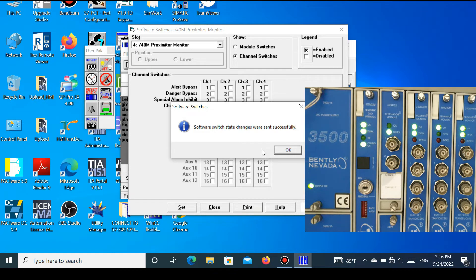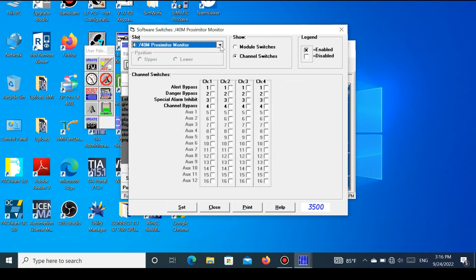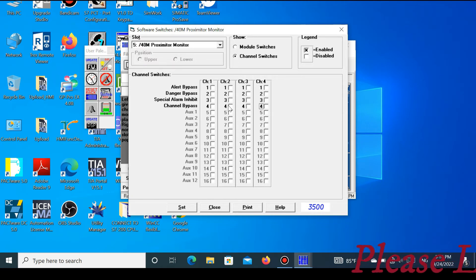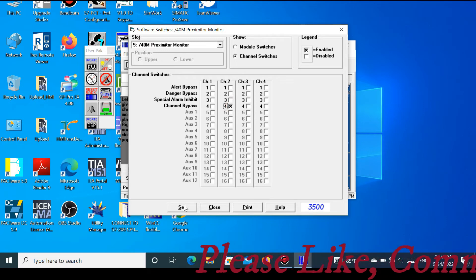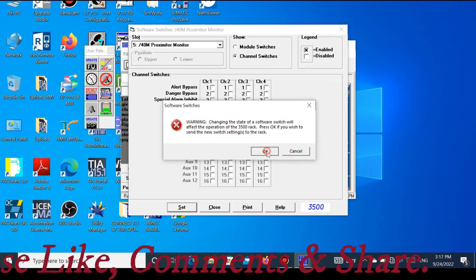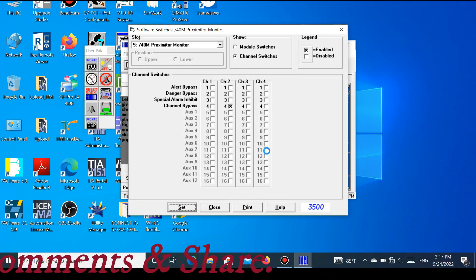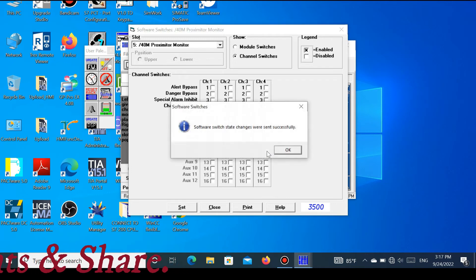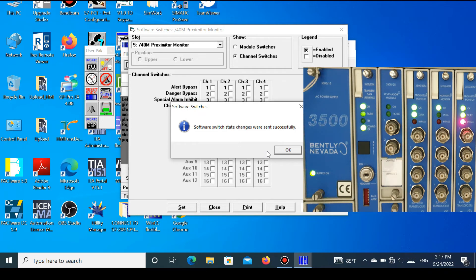I have shown Alert Bypass and Danger Bypass. Now I will show how to bypass a channel. Press the Channel 2 button to bypass the channel and press Set. A warning appears — press OK. After bypassing, the status shows that channel 2 is showing a Bypass alarm, which means the channel bypass was applied successfully.